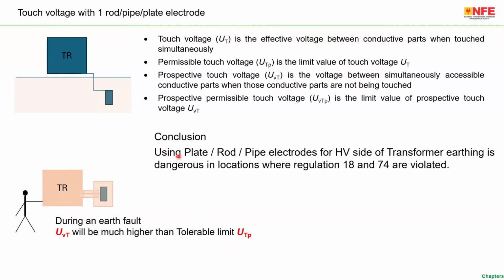Conclusion. Using plate, rod, or pipe electrodes for the high voltage side of the transformer earthing is dangerous in locations where regulations 18 and 74 are violated. What is the violation of regulations 18 and 74? The violation is that there is no metallic fault return path. The continuous earth wire itself is missing. Under that condition, if you are earthing the high voltage side of the transformer through a pipe, a plate or a rod, you are actually in danger, because UVT will be much higher than the limits.